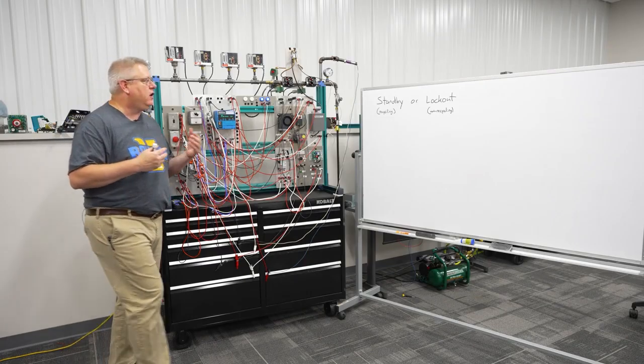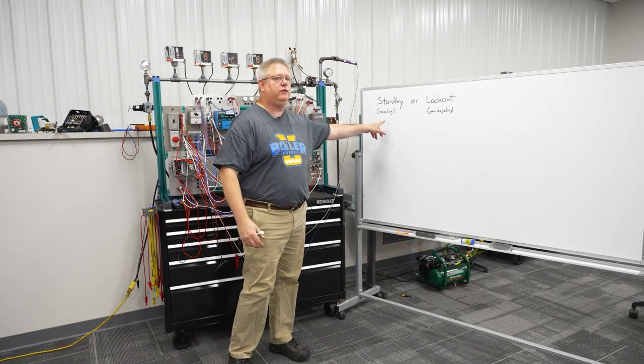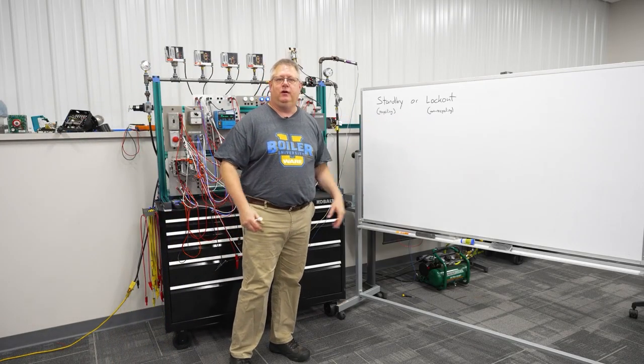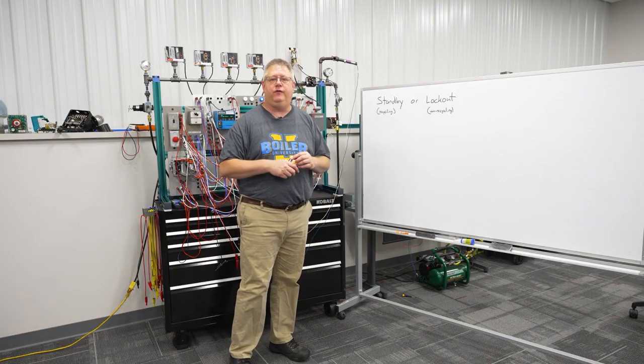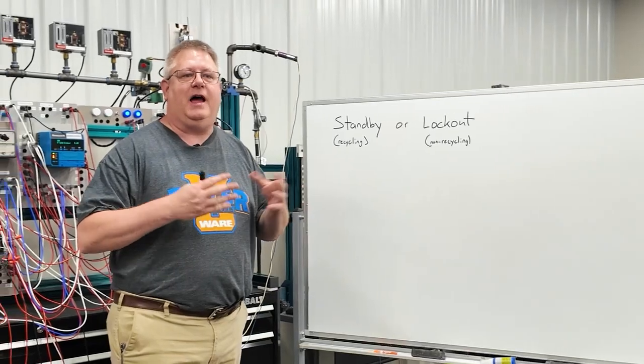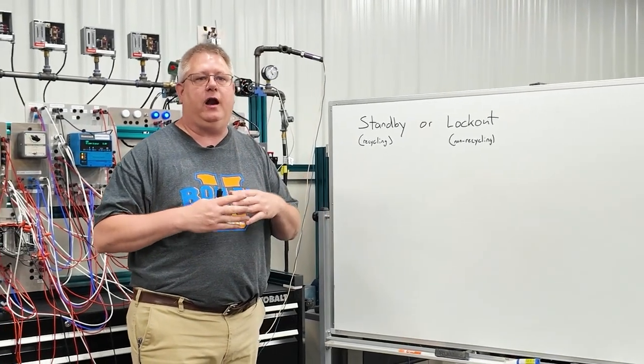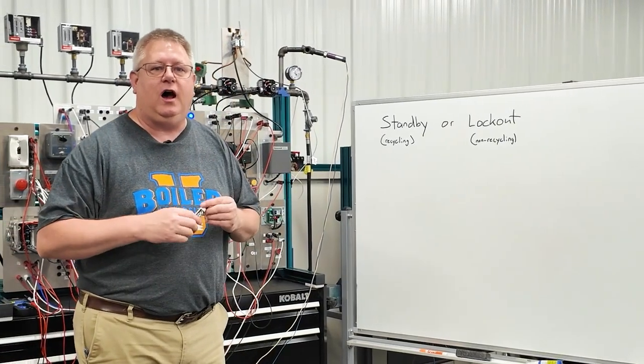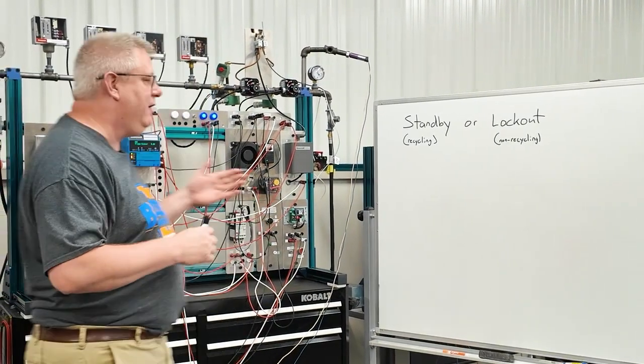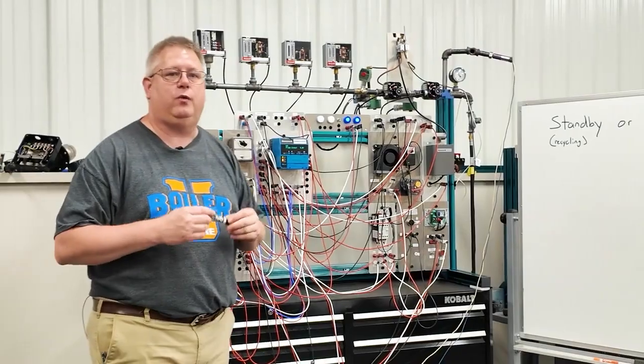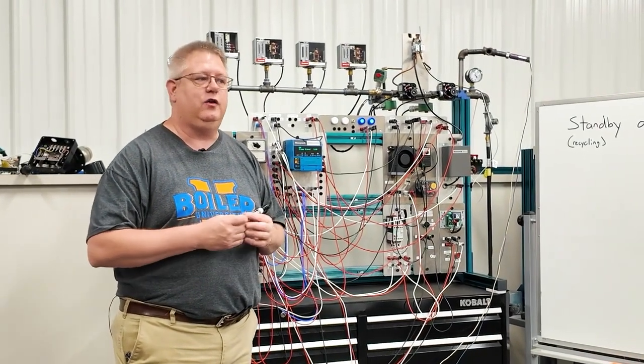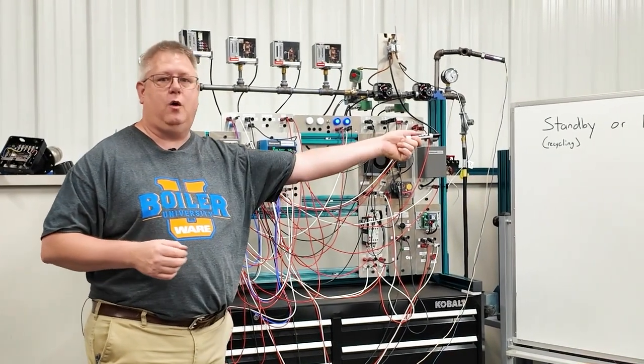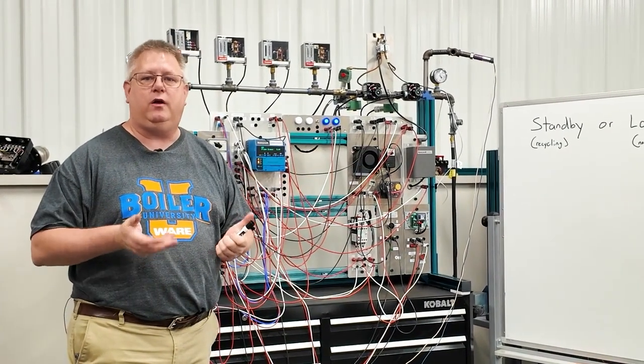Because there are essentially two limit circuits that constitute 90% of our boiler failures. We're out on a gas pressure switch, or we're out on an operating pressure switch. A flame safeguard control will identify which of those limits we're in by going into a standby mode or going into a lockout mode.